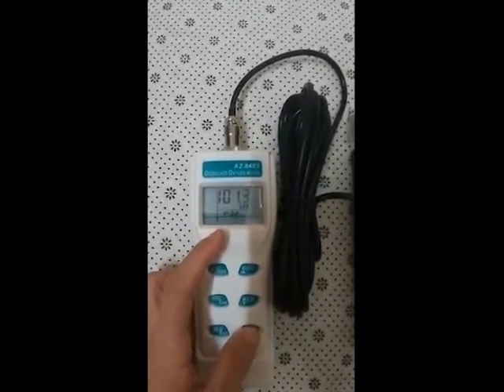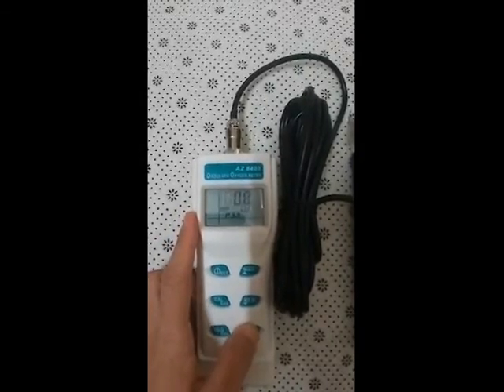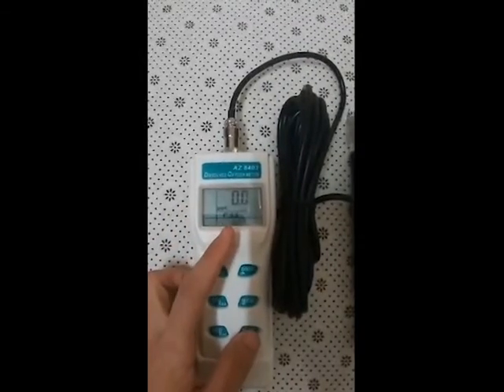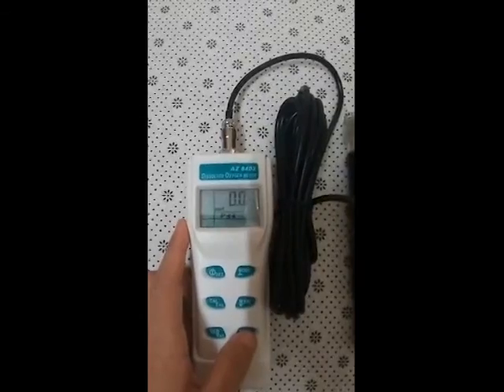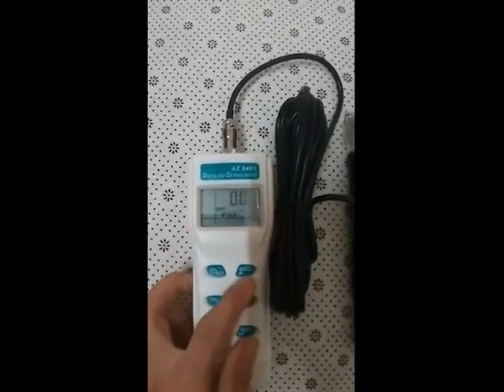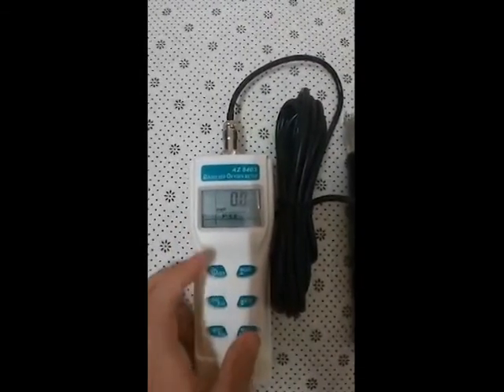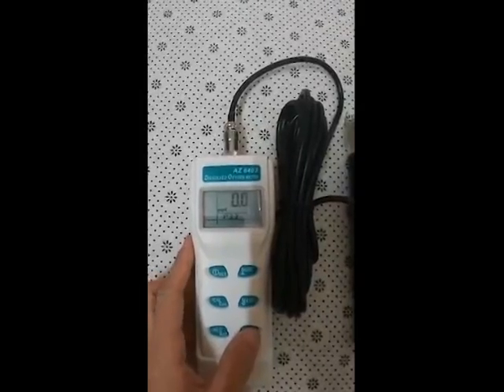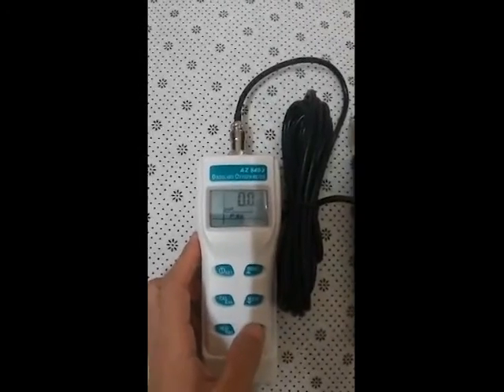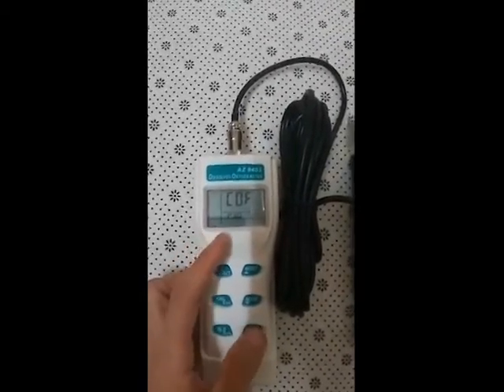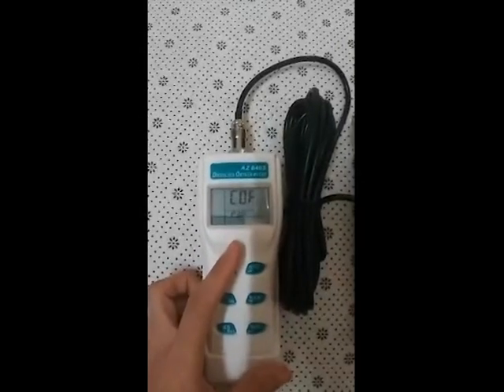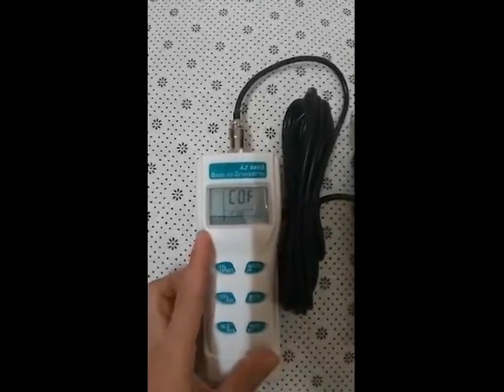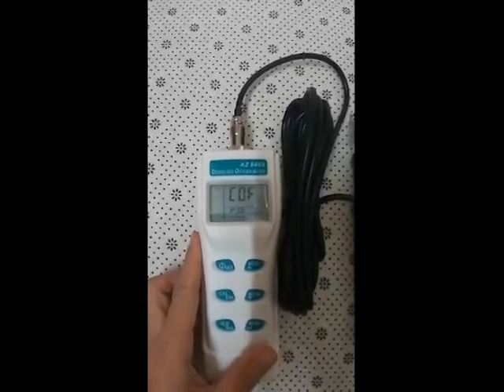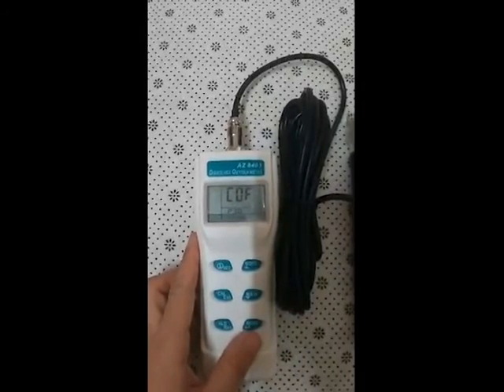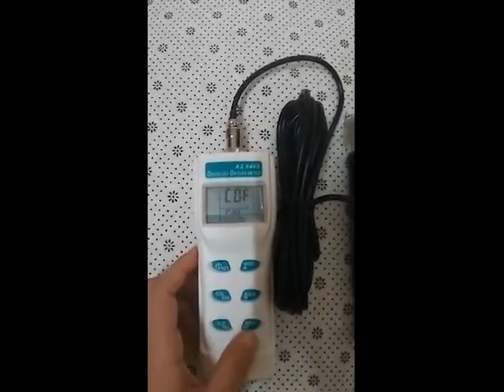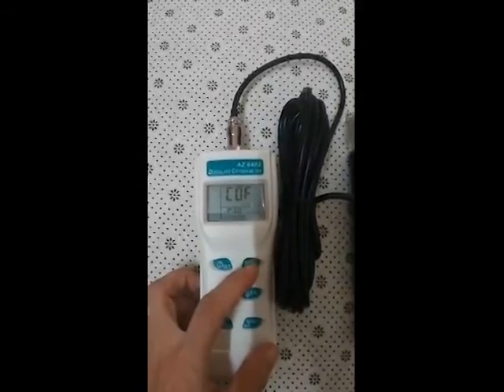After you set this one, you go and set the salinity value. Follow your testing of your seawater or your salty water. You can use up and down to set the value. Then after you finish the setting, you click enter to confirm this value. This coefficient value is only for testing when your solution has special requirements. Ordinarily, if you test fresh water, you don't have to use this function.